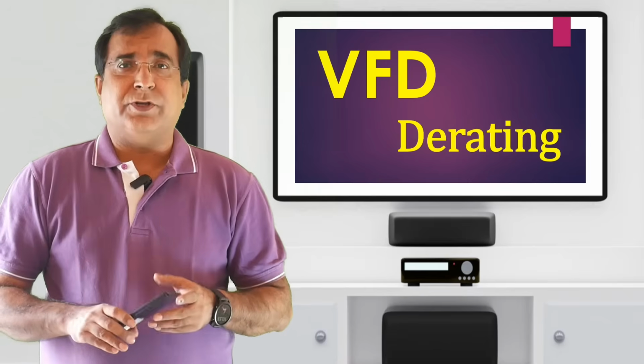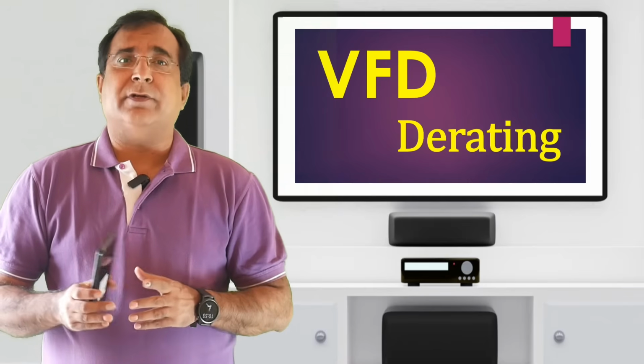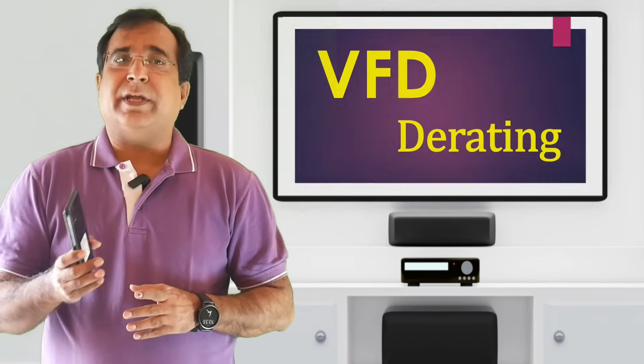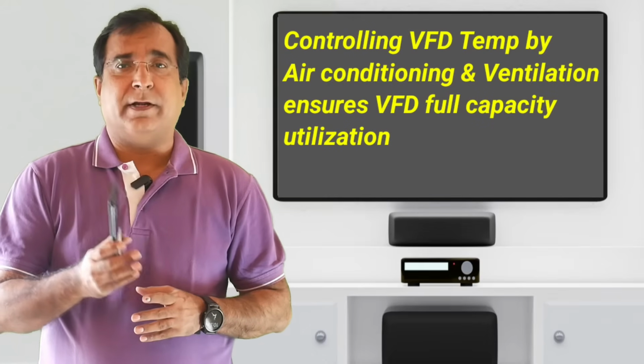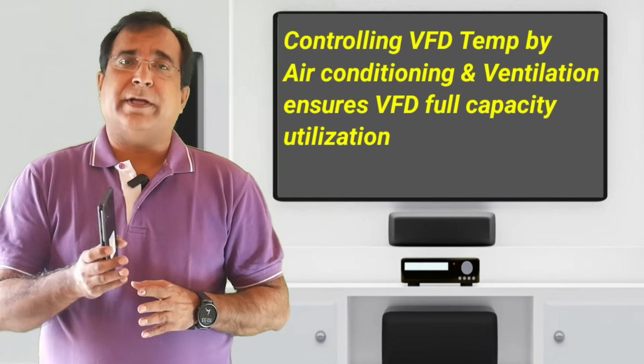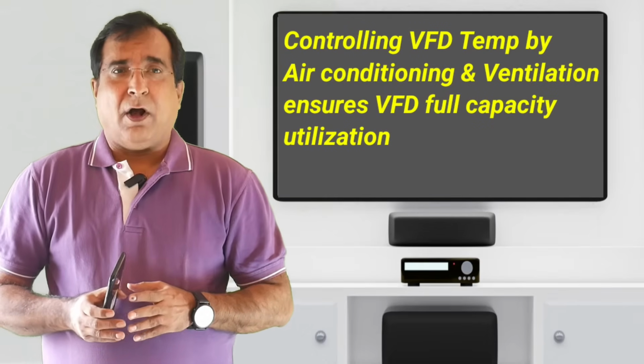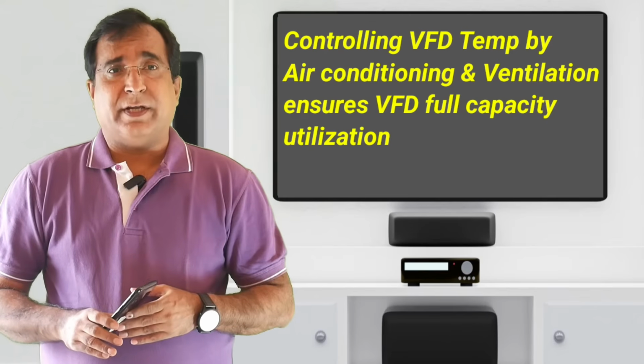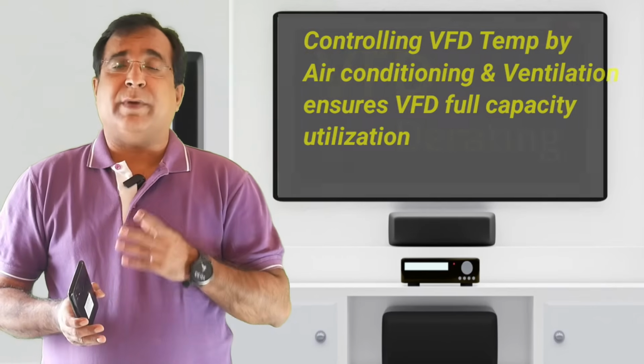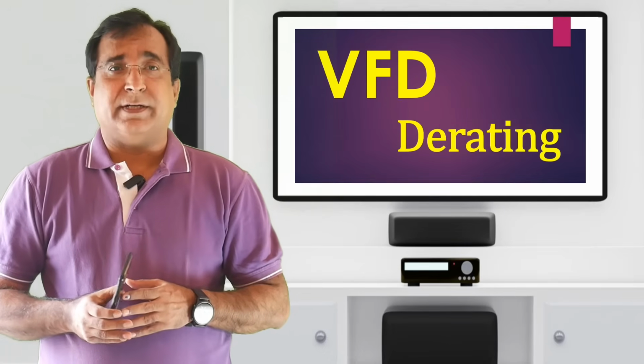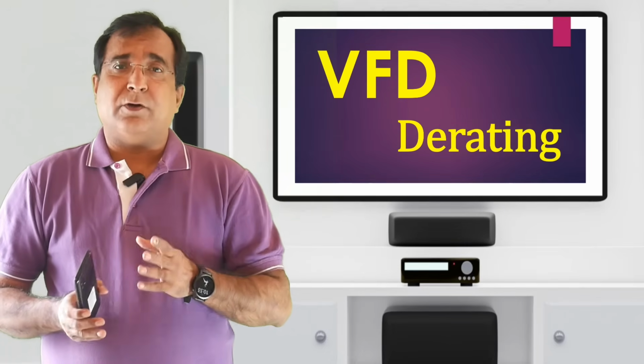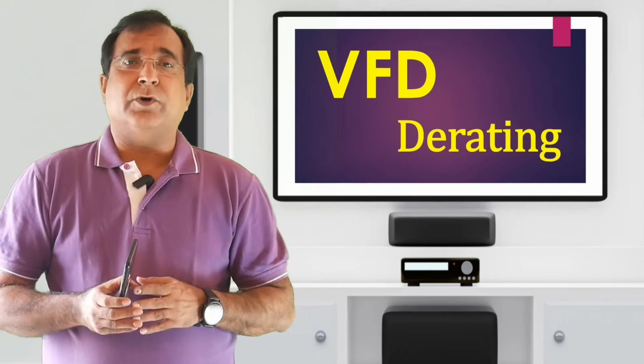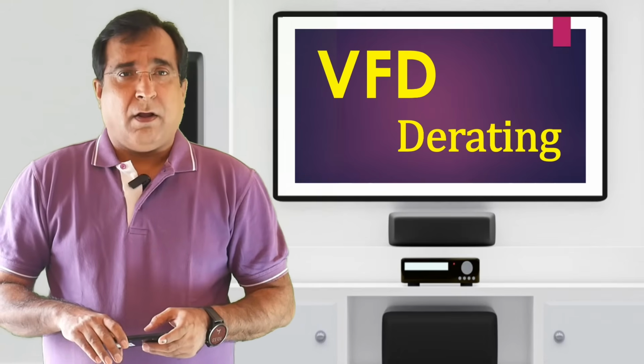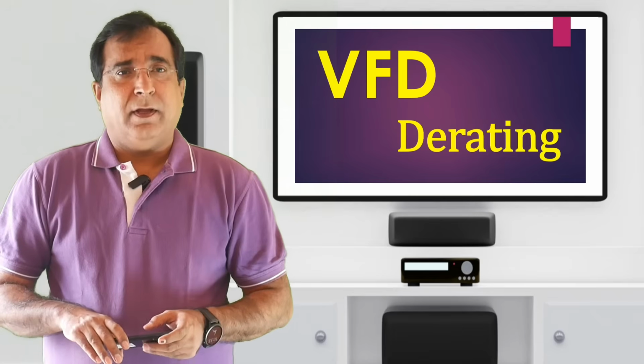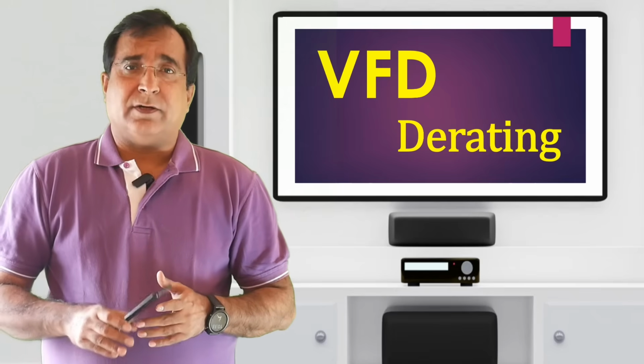Now let's see how this derating effect is tackled. The only solution to ensure the VFD does not trip at an altitude less than 3300 feet is to keep the ambient temperature of the VFD under control with effective air conditioning and ventilation. Also keep additional capacity margin on the air conditioning, so that when one unit fails, the ambient temperature is maintained below 40 degrees centigrade. The temperature of the panel room AC must be monitored in the control room to ensure the AC remains in operation all the time. If the ambient temperature is not in control at a remote location, simply derate the VFD.